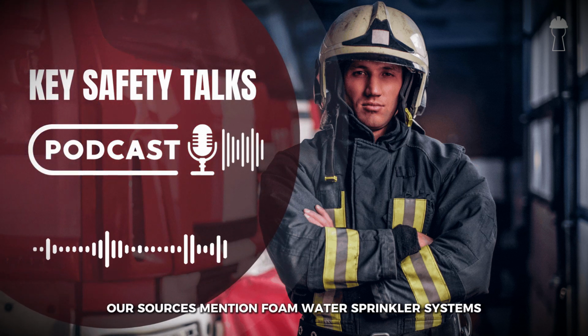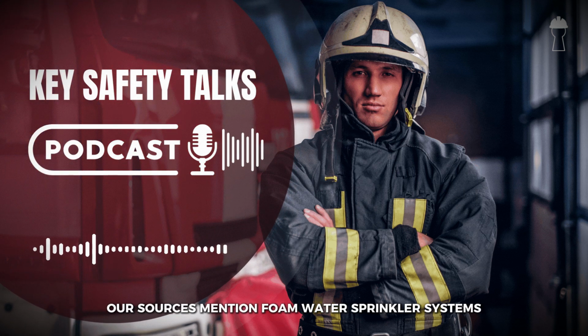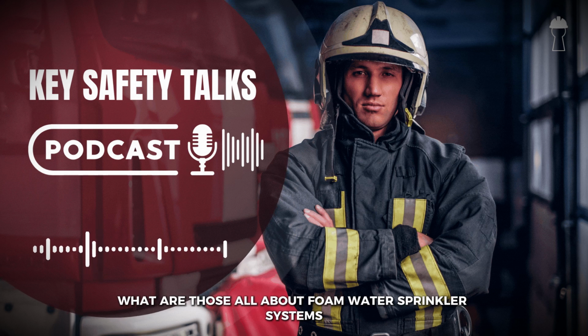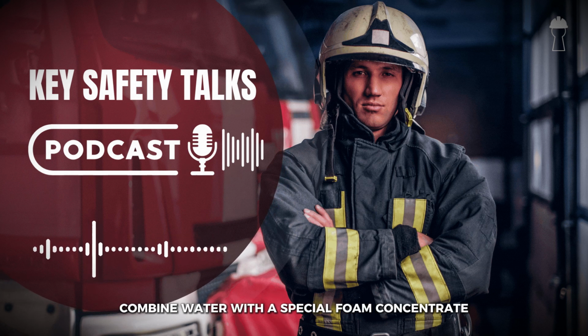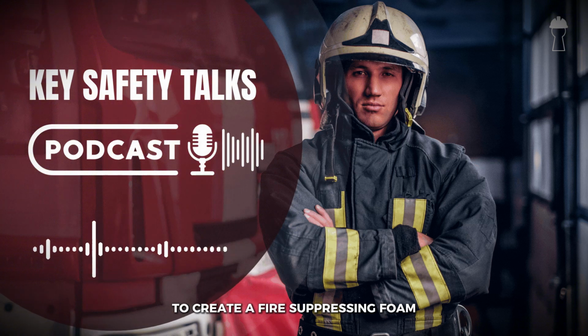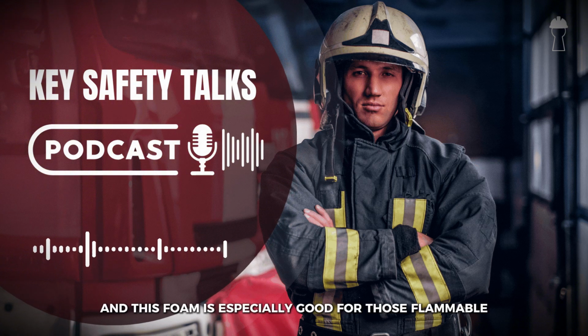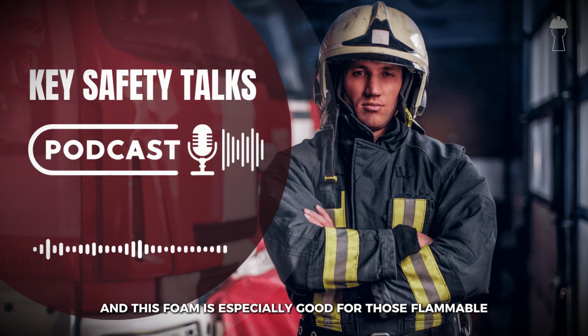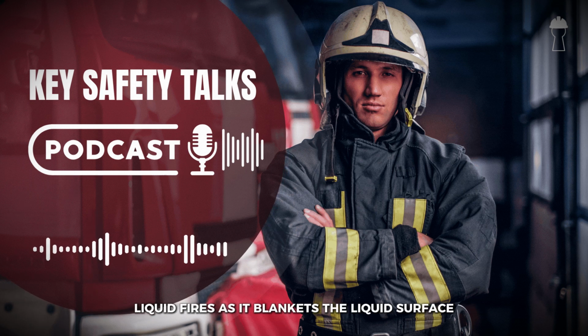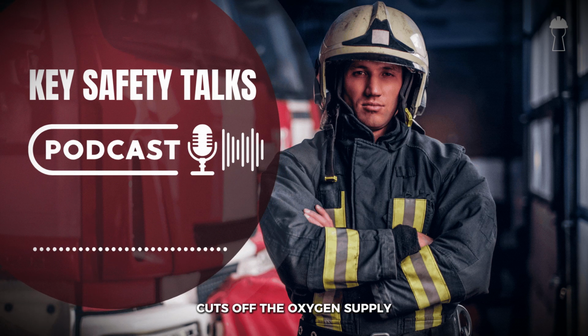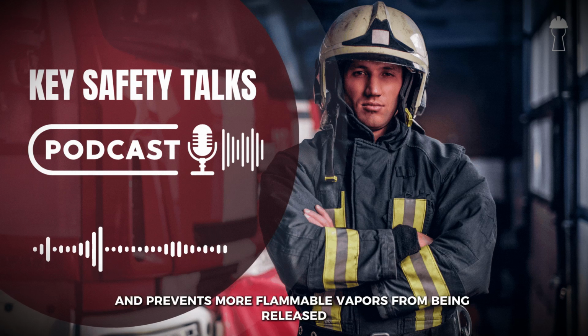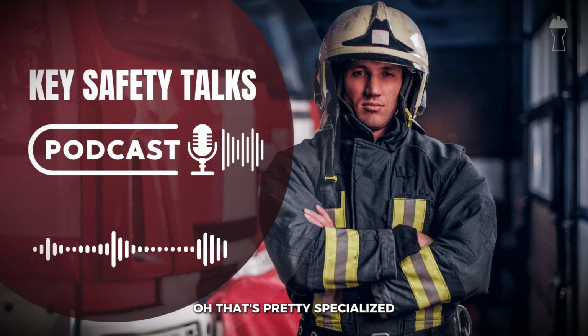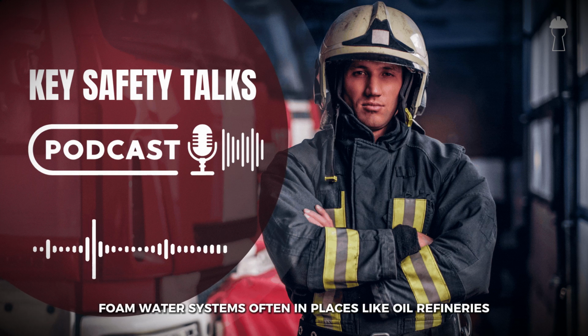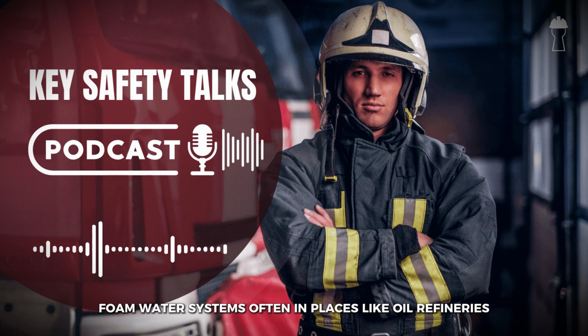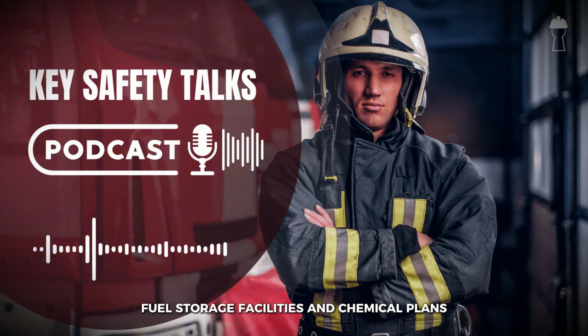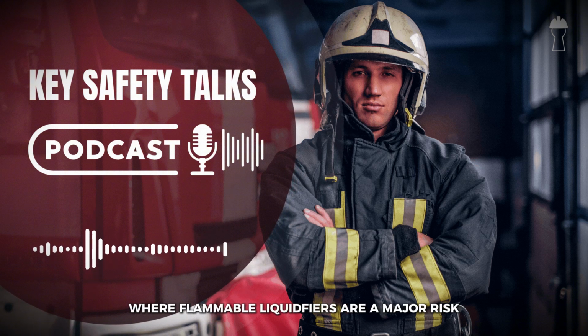Finally, our sources mention foam water sprinkler systems. What are those all about? Foam water sprinkler systems combine water with a special foam concentrate to create a fire-suppressing foam. And this foam is especially good for flammable liquid fires as it blankets the liquid surface, cuts off the oxygen supply, and prevents more flammable vapors from being released. Oh, that's pretty specialized. It is. You often see foam water systems in places like oil refineries, fuel storage facilities, and chemical plants where flammable liquid fires are a major risk.